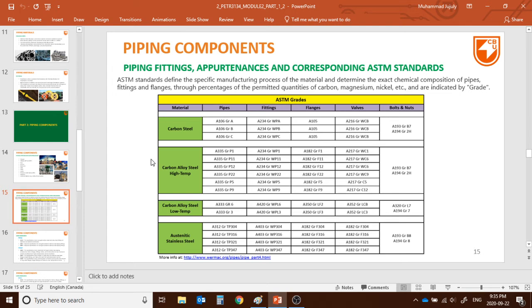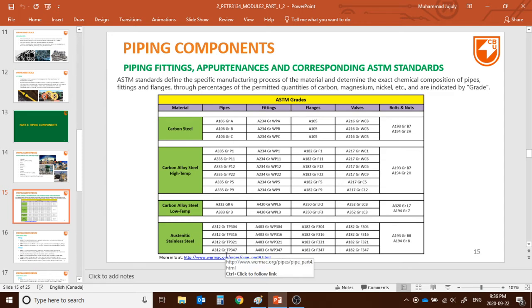For example, if your supervisor tells you to design a piping system for carbon steel grade A106, you use this matrix: the main piping material is A106, so the flanges follow ASTM A105, valves follow A216, and fittings follow A234. That's exactly why this matrix is important — you can quickly find what standards are needed.